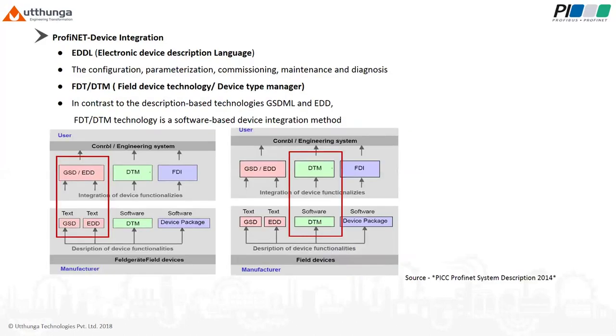Electronic Device Description Language. The configuration, parameterization, commissioning, maintenance, and diagnosis of the device from the engineering system requires a more efficient language. Thus, EDDL came into the picture. The EDDL technology enables a host system manufacturer to create a single engineering environment that can support any device from any supplier using any communication protocol. EDDs are structured text files that contain configuration information written in electronic device description language. These are also provided by the manufacturers.